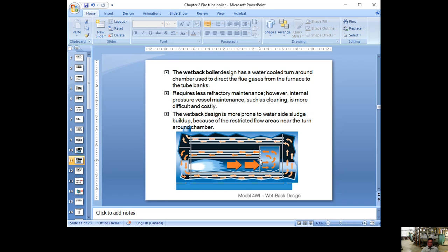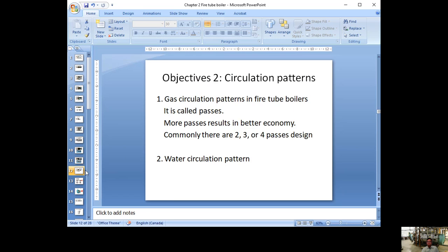Because the most intense heat is on the first pass, and the wet back has water to absorb that heat, by the time flue gas reaches the back dry door on later passes, the heat is not as intense as the first pass. However, any time you make water turn around in a compartment there can be scale and dirt accumulating — just like an elbow in a pipe — and on the turn-around chamber there's a lot of dirt buildup.